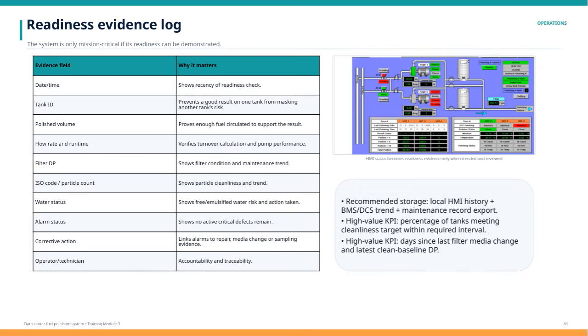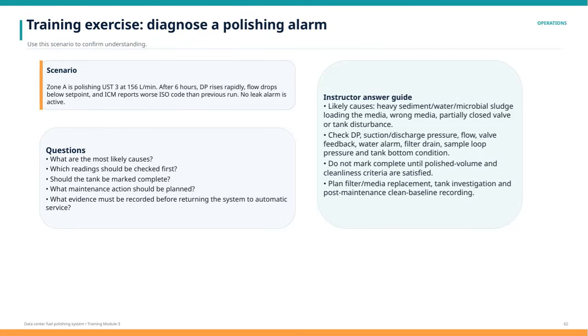In this training exercise, we are going to diagnose a polishing alarm in the fuel polishing system. The scenario involves Zone A polishing underground storage tank 3 at a flow rate of 156 liters per minute. After 6 hours, we notice that the differential pressure rises sharply, the flow rate drops below the set point, and the integrity control module reports a worse ISO code than in the previous run. Interestingly, there is no leak alarm active in this situation.